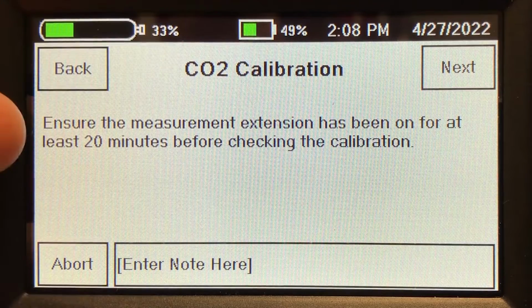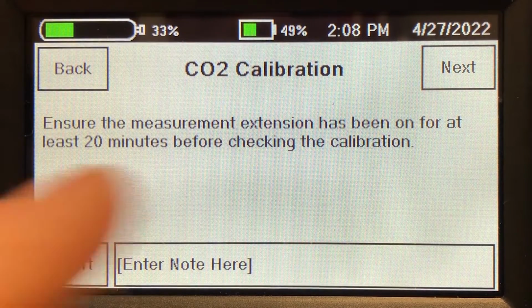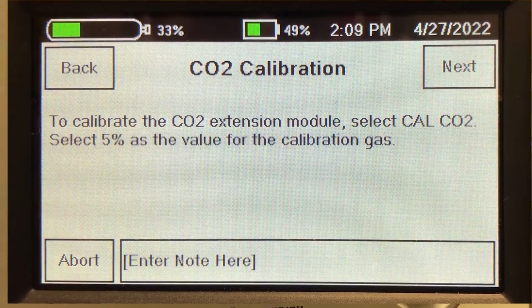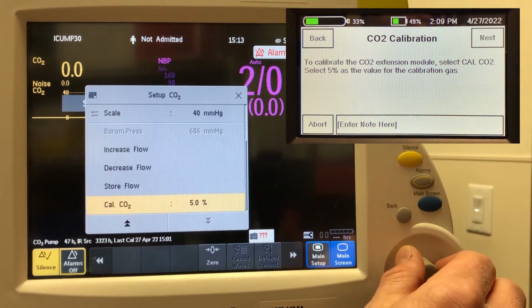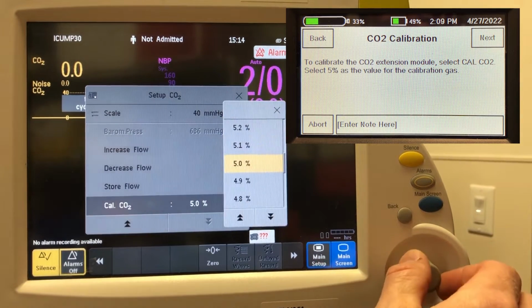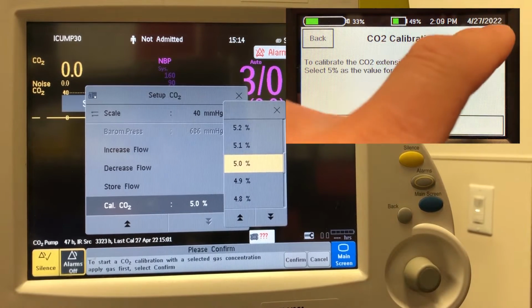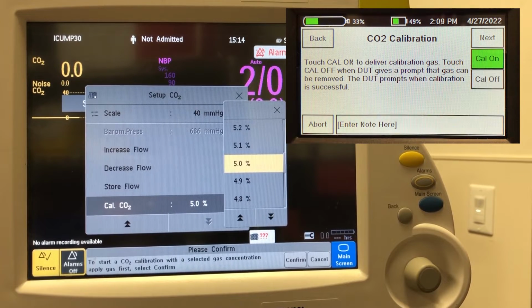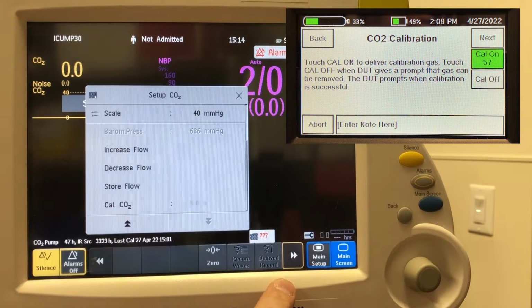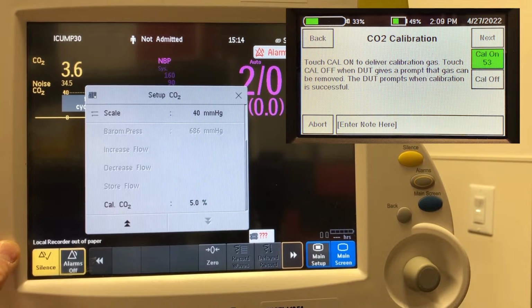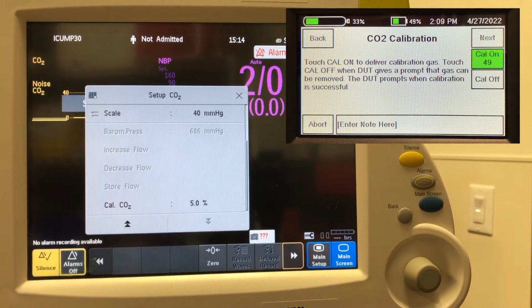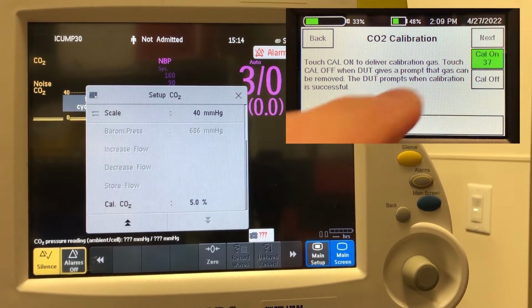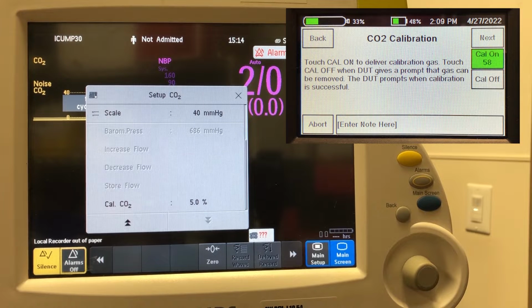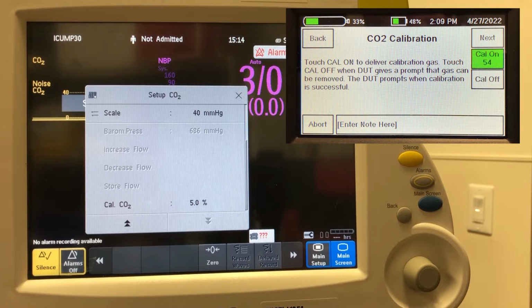Before we do the CO2 calibration, we want to make sure the extension module has been on for at least 20 minutes. This module has been, so I can move on. This tells us to go into Cal CO2. Select Cal CO2 on the monitor, and then we select 5%, and then we touch Cal on to deliver calibration gas, and we touch confirm on the monitor. If we look over here, we can see that it will tell us that its CO2 calibration is in progress. You can see the smart tank is counting down. This is so you don't forget that it's on and run a calibration gas bottle empty. If the device you're testing needs more time, you can just touch it and it resets the timer without disrupting the gas flow that's being fed to the monitor.